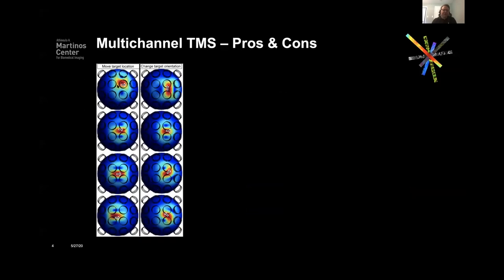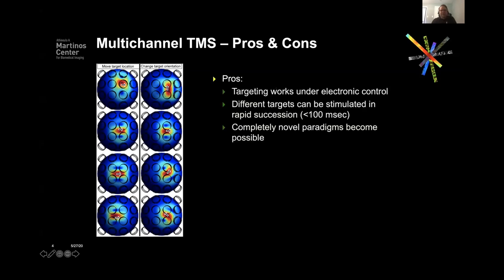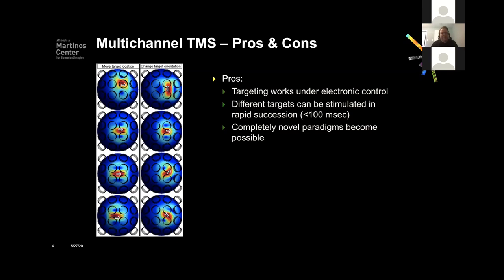The multi-channel system tries to do that differently. Instead of using one or two coils moving around, you build an array of coils and adjust the currents to synthesize an electric field hotspot by combining fields from multiple coils into the desired location. If you're able to do this, you can quite rapidly shift both the target location and orientation of the electric field. The pros are that it works under electronic control, so it's relatively quick to move the target, and it enables new types of TMS paradigms.